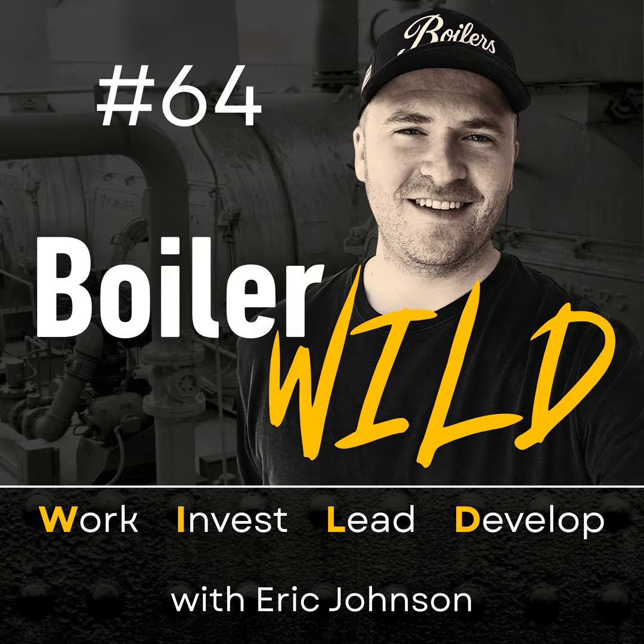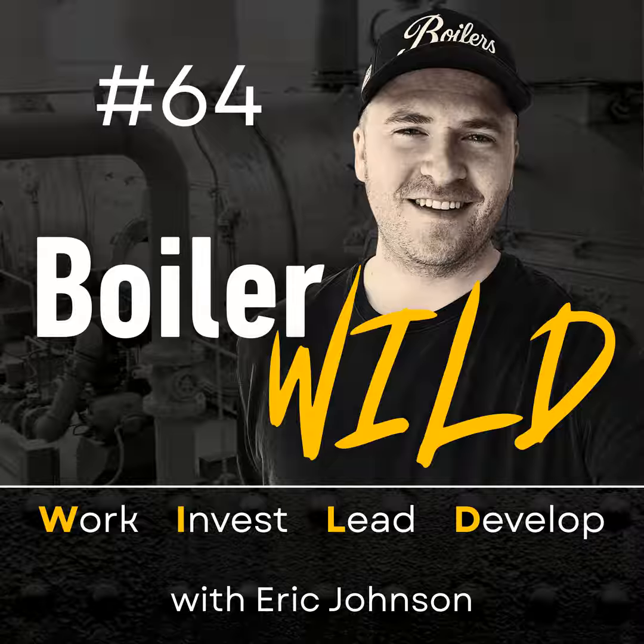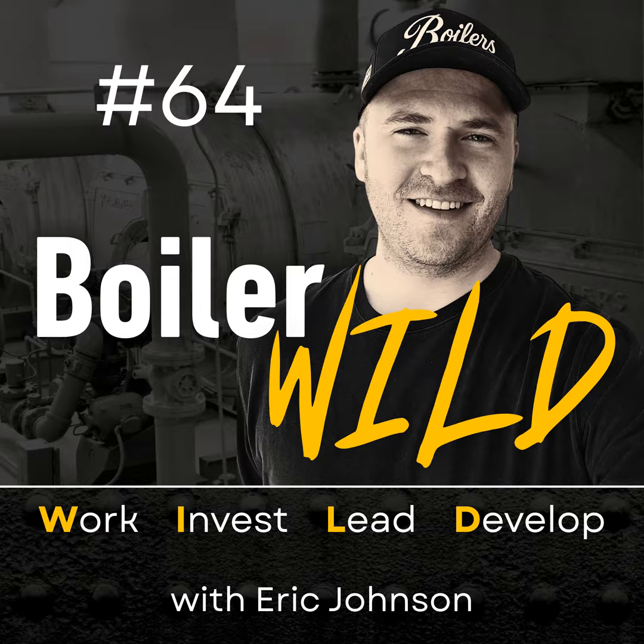Then, you got to pull out your meter. And of course, it's probably Friday at 2:00. You're like, it's giving me issues here. And you start troubleshooting. And then of course, you're an expert troubleshooter, and you have a perfect wiring diagram that's laminated and correct for the equipment in front of you. So you can easily find the issue, and you look at it, you check a couple terminals, and you're like, high pressure limit is tripped.